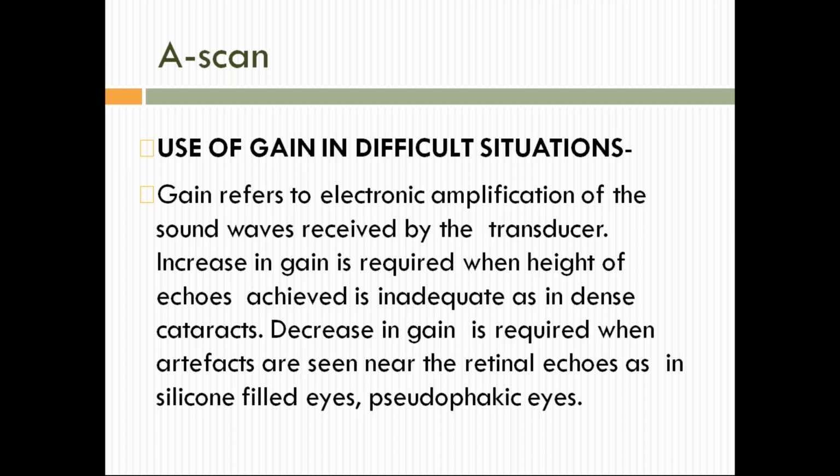Use of gain in difficult situations. Gain refers to electronic amplification of the sound waves received by the transducer. An increase in gain is required when the height of echoes achieved is inadequate, as in dense cataracts. A decrease in gain is required when artifacts are seen near the retinal echoes, as in silicone-filled eyes and pseudophakic eyes.